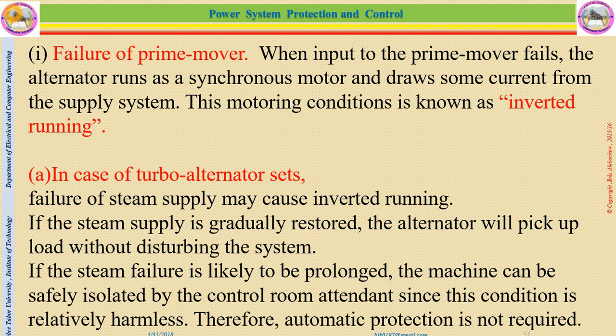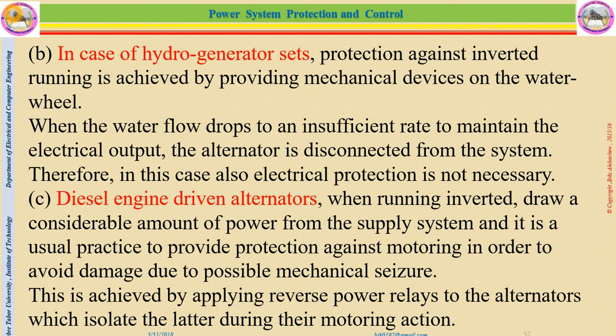If the steam failure is likely to be prolonged, the machine can be safely isolated by the control room attendants instead of by automatic protection, because this condition is relatively harmless. Therefore, automatic protection is not required for failure of prime mover in turbo generators. In the case of a hydro generator, protection against inverted running is achieved by providing a mechanical device on the water supply. When the water drops to an insufficient rate to maintain the electrical output, the alternator is disconnected from the supply system. So in this case also, electrical protection is not necessary.